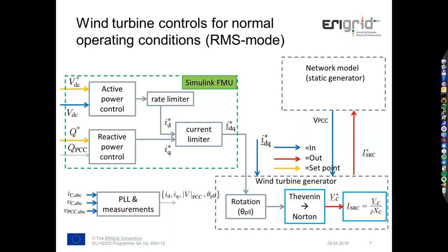Here we are running in reactive power control instead of voltage control. The main idea is that during faults, we can boost this reactive current proportionally to the depth of a voltage dip, so we can support the voltage.